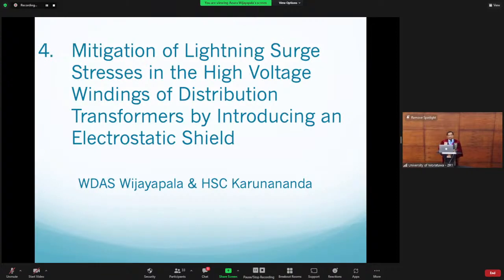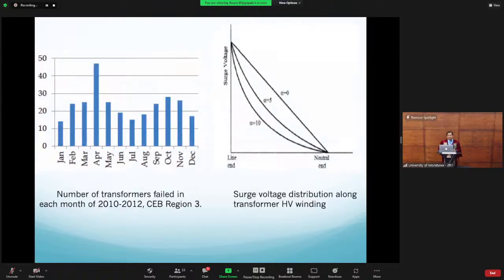The fourth research out of the 10 I am presenting this afternoon. The fourth one is mitigation of lightning surge stresses in the high voltage windings of distribution transformers by introducing an electrostatic shield. I did it with engineer H.S.C. Karunananda. And you can see in the left bar chart the number of transformers failed in CEB region 3. CEB has 4 regions. This is region 3 data. And you can see transformers failed due to a variety of reasons. But when you look at April, there is a substantial increase in the failures. And it is due to, as we all know, the high lightning and thunder. April is a month we get a lot of lightning and thunder. And so these additional failures are mostly attributable to failures by lightning surges.